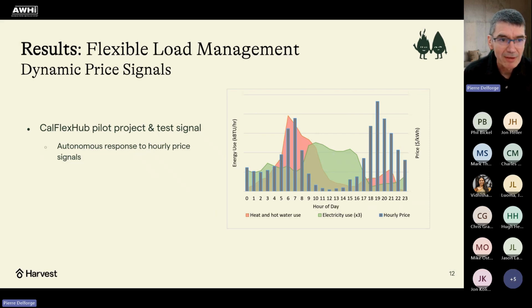You can see that most of the electricity use was in that valley where you have very low prices, and we're still a little bit on peak. Fan energy use and circulator pump energy use can't be shifted, so that remains. And sometimes we do need to run the heat pump outside of these solar hour windows because there's just not enough hours in the middle of winter during the solar window, but it's minimal.